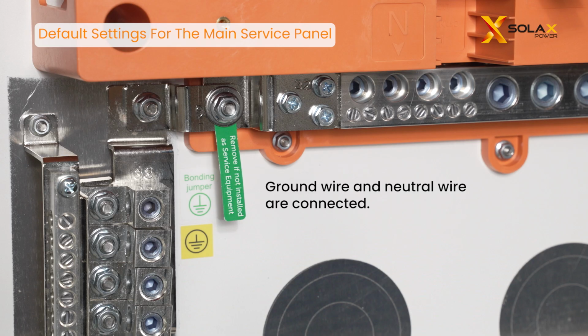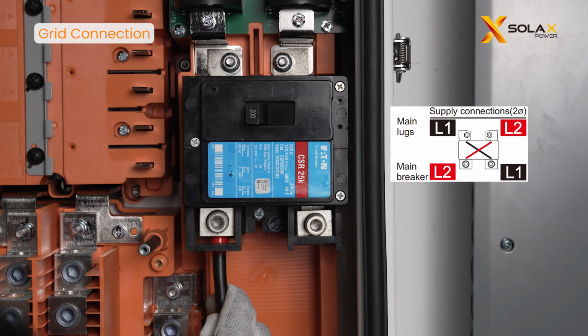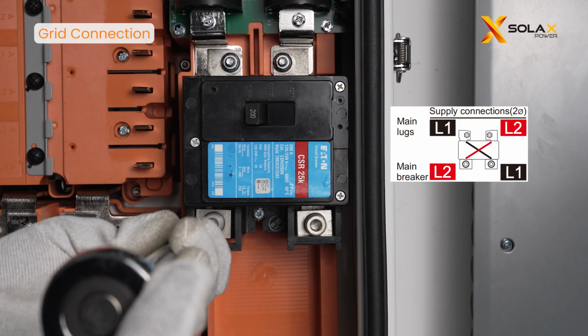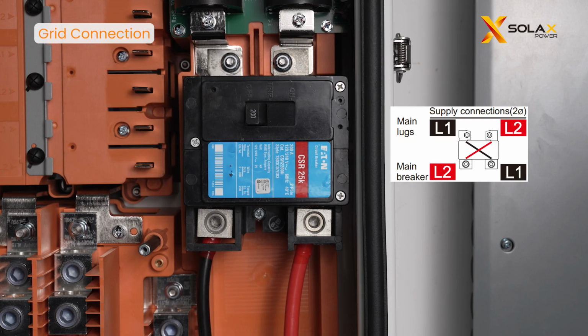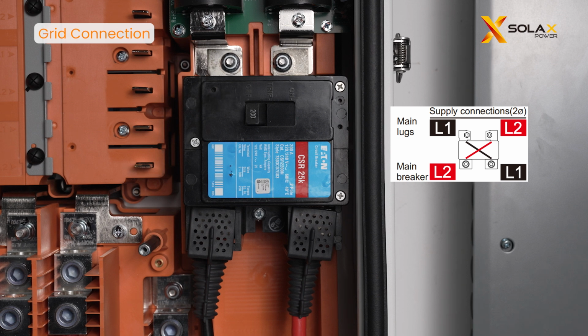In the service equipment scenario, do not disconnect the bonding jumper, and the Eaton breaker must be installed for grid connection. Connect the grid cables to the grid ports and cover the main breaker's plastic safety caps. For other connections, please refer to the previous wiring.